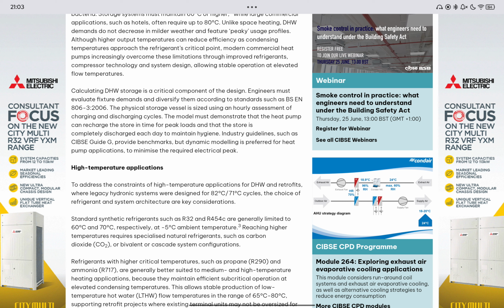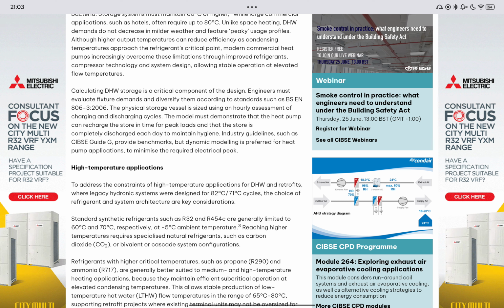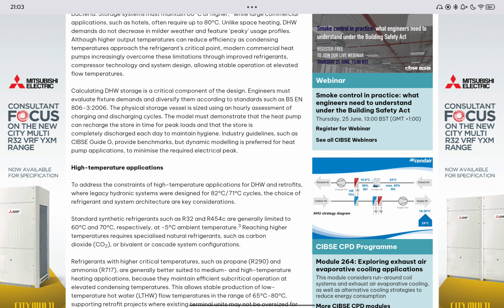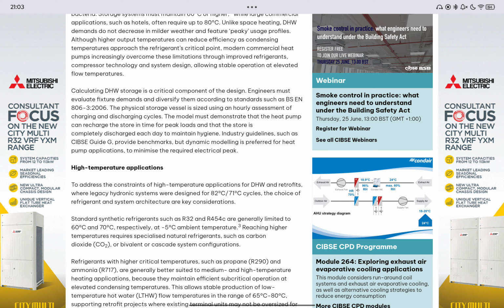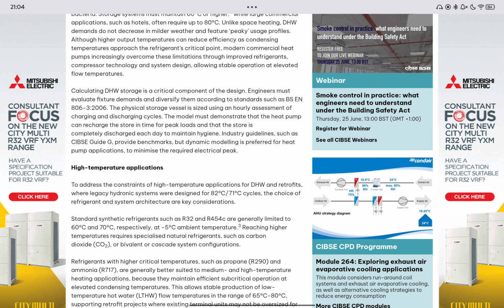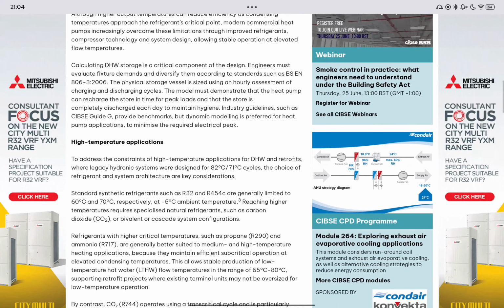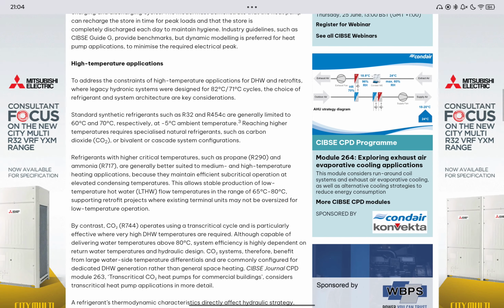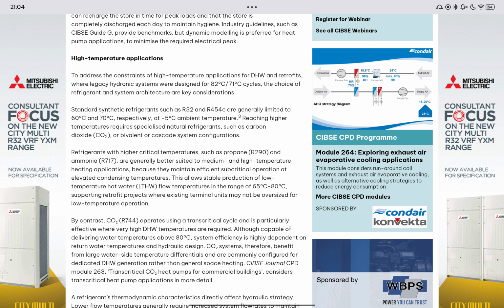The model must demonstrate that the heat pump can recharge the store in time for peak loads and that the store is completely discharged each day to maintain hygiene. Industry guidelines such as CIBSE Guide G provide benchmarks, but dynamic modelling is preferred for heat pump applications to minimise the required electrical peak. High temperature applications.